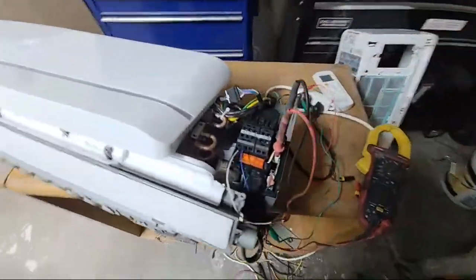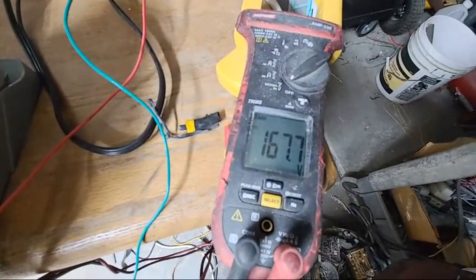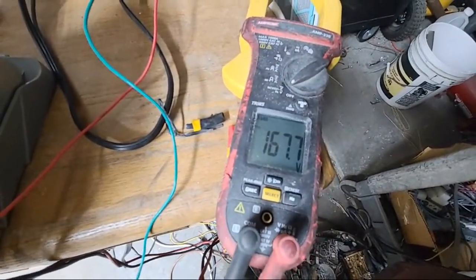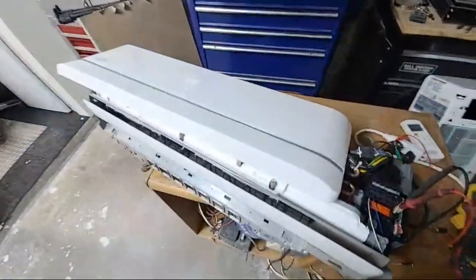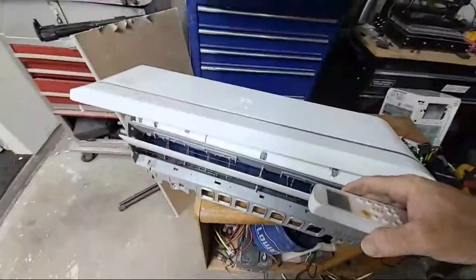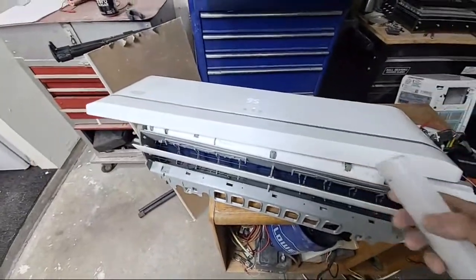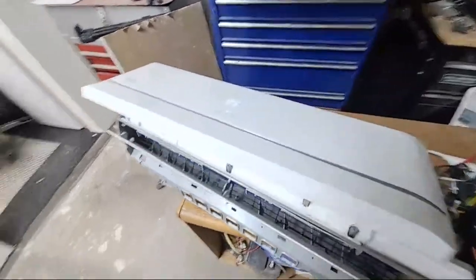120 volts AC, and so the resulting DC at the fan motor through the rectifier is only 167 volts, 170 basically what it runs at. Oh, looks like it might be going back on memory here. There it goes, the fan's going to start.